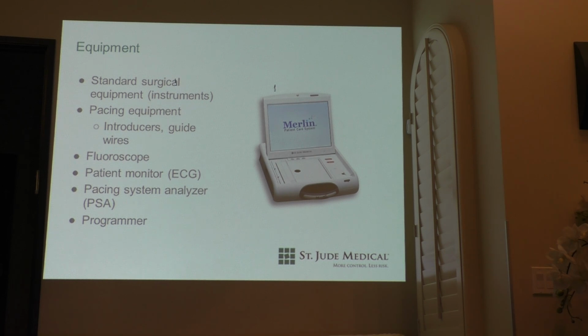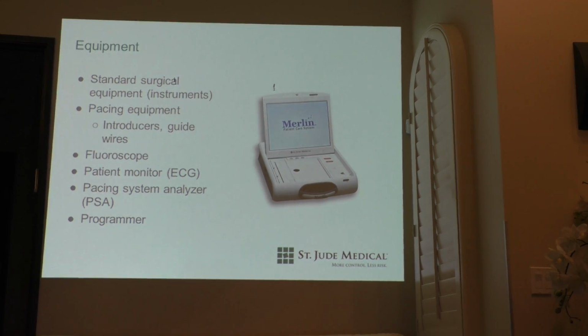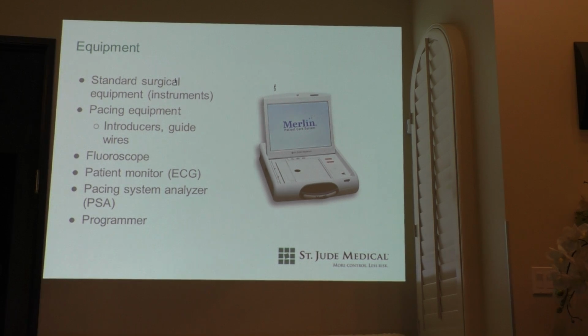So we use what's called a pacing system analyzer. It's like a glorified temporary pacemaker. I'll pull it up here for you. What it allows us to do is to apply paced rhythm at different rates, so 60 beats, 90 beats, 100 beats a minute, at different outputs, so you can go anywhere from 0.2 volts all the way to 10 volts, and we can also listen for sensed rhythm. We can measure what it looks like.